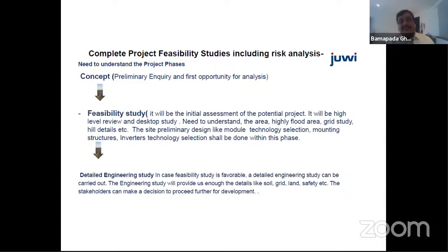Besides that, for the project sites, the inverter technology question comes up: string technology or central inverters. If the contour is highly undulated land, for 50 megawatts or less it's always better to go with string inverters, because of generation loss or mismatch loss. Again, it depends on capital cost and generation, how much generation we will get versus what the capital cost would be.